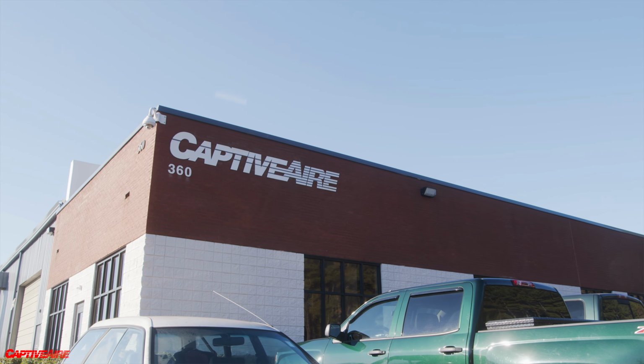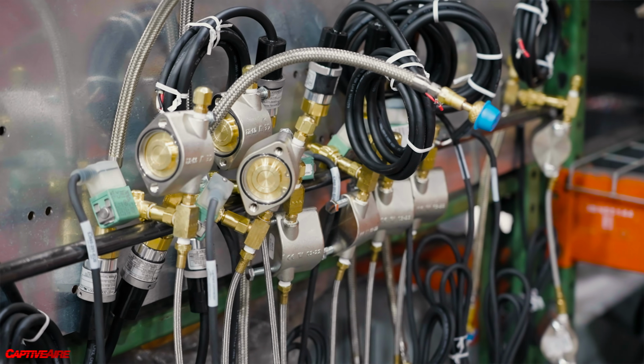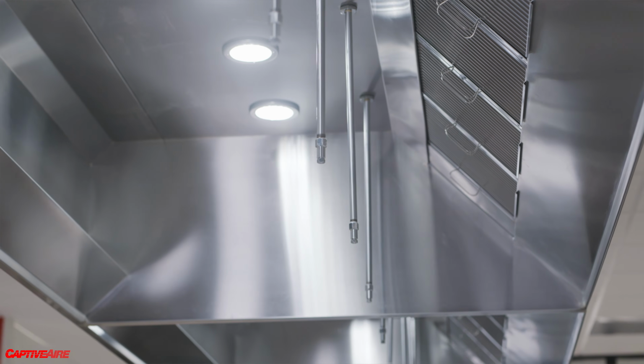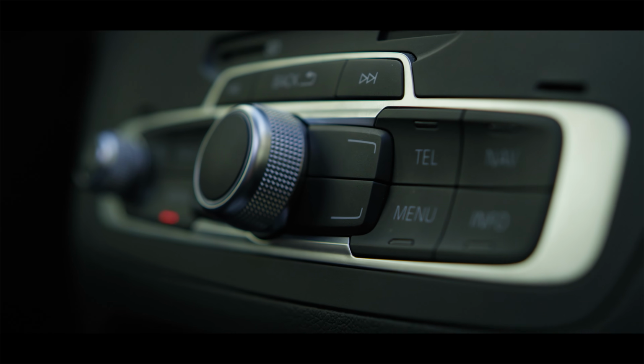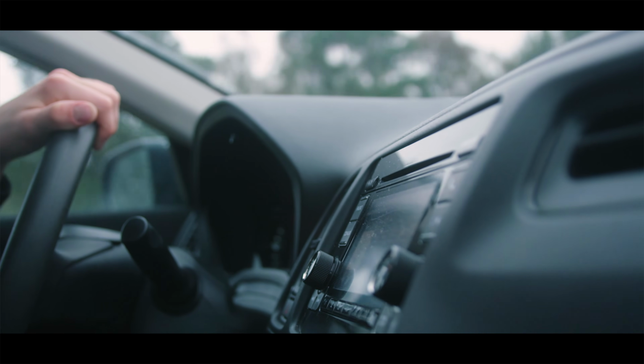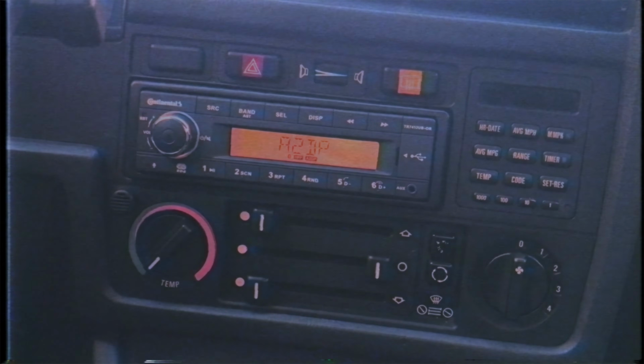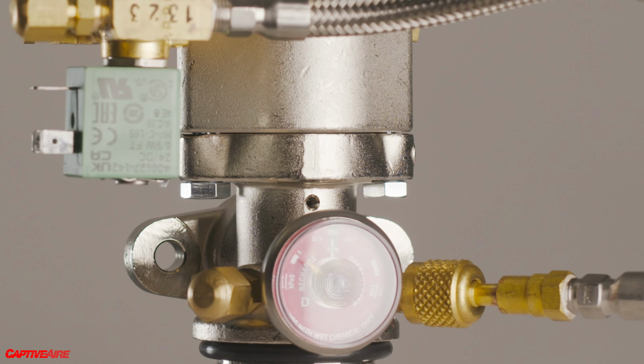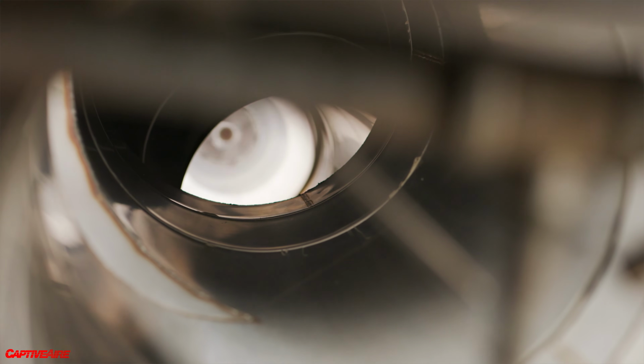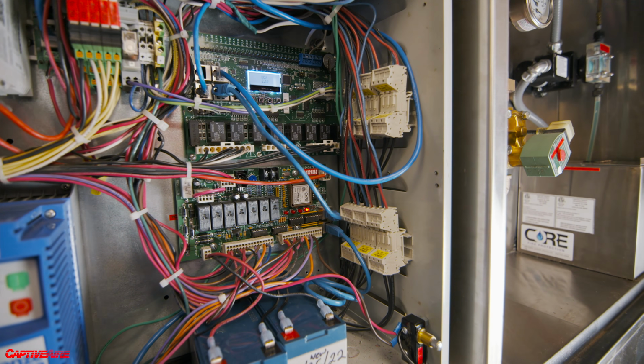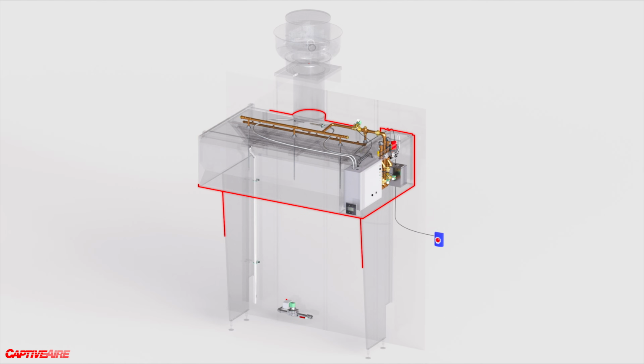So most fire suppression systems are third-party systems. They're aftermarket components. Where at CaptiveAire, we've taken a different approach. Our suppression systems are OEM components, and they're designed to work with the hood and with our controls. One way to look at this: in modern times, how many people do you know that go out and buy an aftermarket radio and put it in their car anymore? It's probably very few. Where if you go back 20 years ago, aftermarket radios were very common. So we've taken the approach that we're going to integrate the best technology into our hoods and our systems as possible. And we know exactly how that suppression system works with our exhaust system and with our hood and with controls. So we're trying to develop a complete system that brings the ultimate level of safety to kitchens.